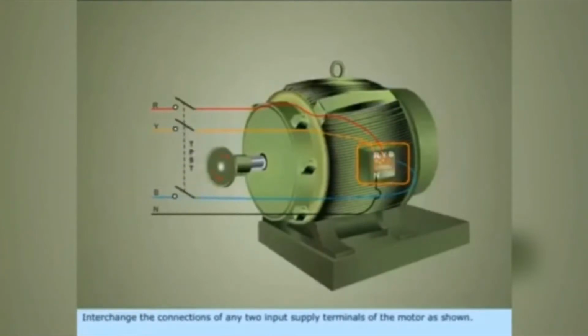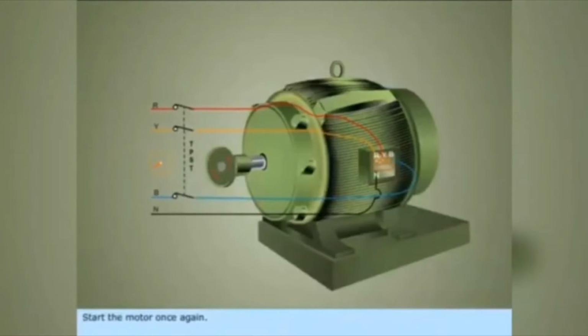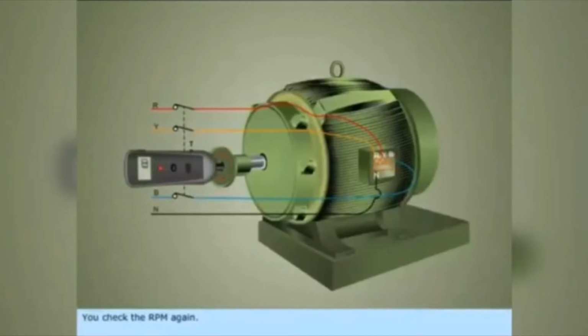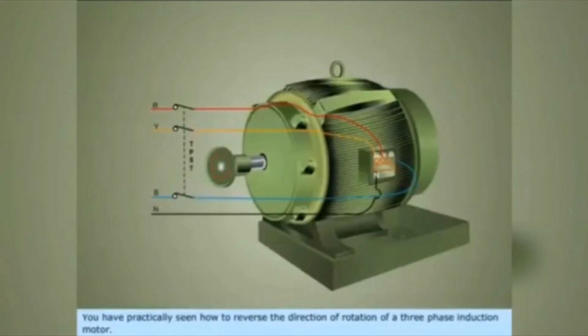Interchange the connections of any two input supply terminals of the motor as shown. Start the motor once again. You can now see that the motor shaft is rotating in the anti-clockwise direction. You check the RPM again. You can see that the speed obtained is the same as in the previous case. You have succeeded in reversing the direction of the motor. You have practically seen how to reverse the direction of rotation of a three-phase induction motor.